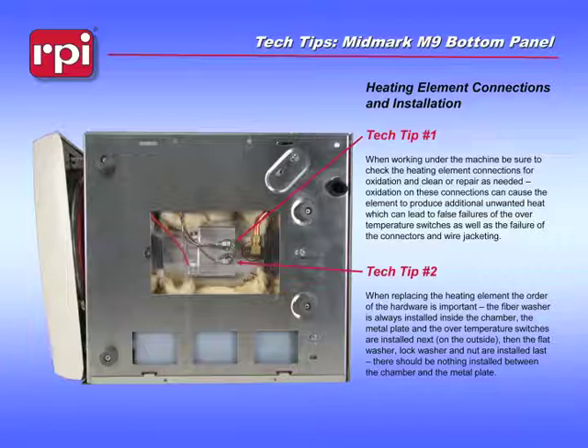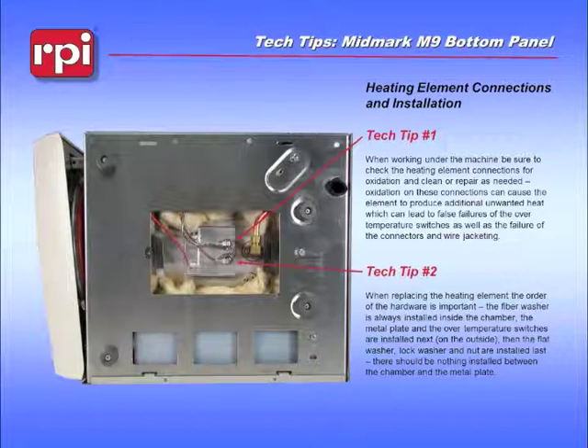So now we're going to go through some technical tips that we have found by talking to various customers, things that we pay attention to and we tell our customers to pay attention to when they're working on the machine. In order to do this, we basically have drained the machine, we've turned it on its side, and we have removed a plate that's mounted on the bottom so you can actually see the bottom of the sterilizer. So when working under the machine, you should pay attention to a few things.